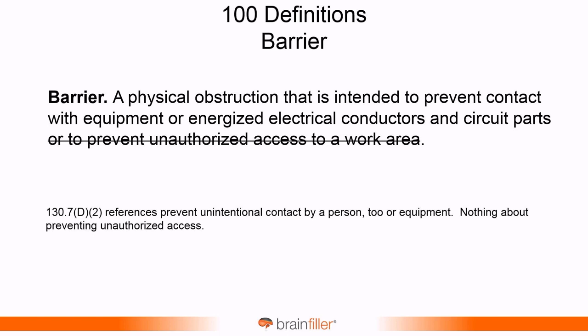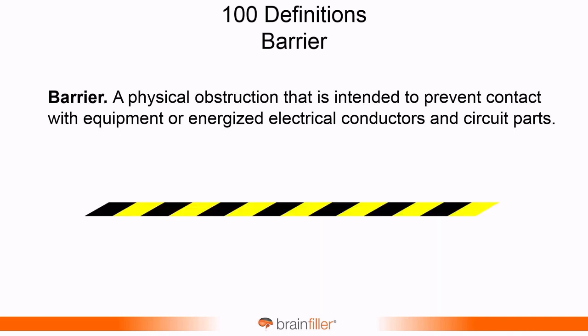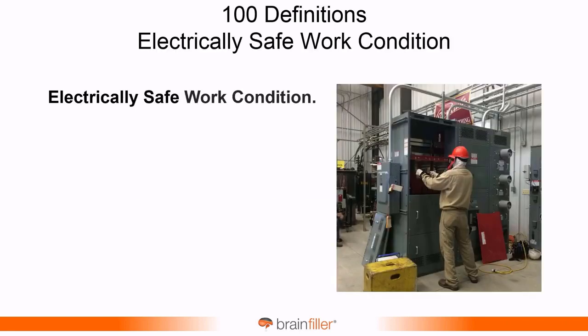Definition of a barrier. There was a change made here, and this was to align with some other references within NFPA 70E. So, for example, in this case, the barrier, the last words, to prevent unauthorized access to a work area. That really wasn't what the barrier was all about. It's to prevent contact with equipment or energized electrical conductors. And so the definition for barrier now states that it's an obstruction intended to prevent contact with equipment or energized conductors and circuit parts.